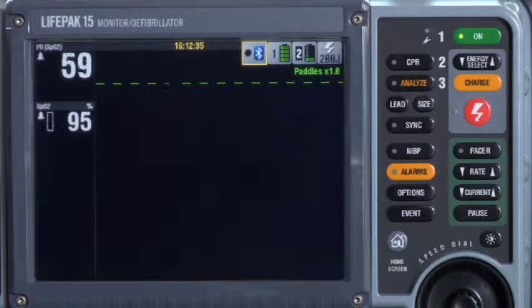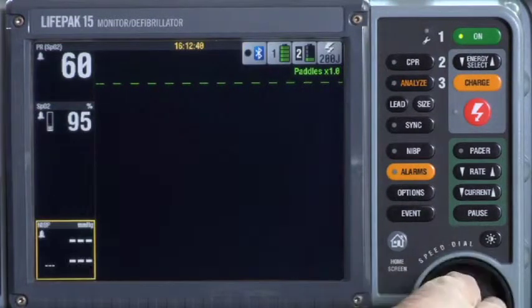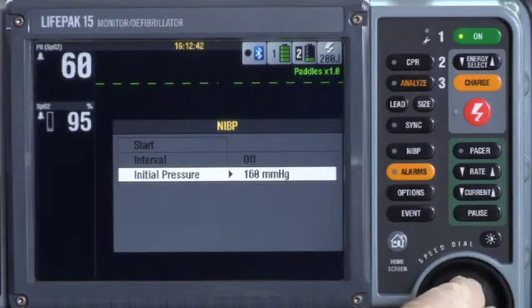The default inflation pressure is 160 millimeters of mercury, but if you have a pediatric patient or you suspect your patient's blood pressure is higher than 160, you may need to change the default inflation pressure. To change it, use the speed dial to select NIBP. Select Initial Pressure, then select the pressure you want.